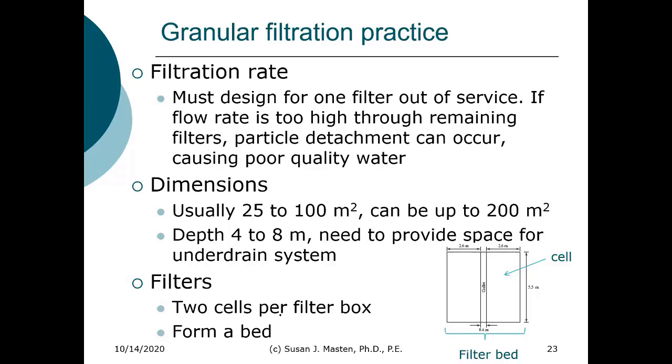And you need to remember that in your design. When in the East Lansing wastewater treatment plant, when they designed those filters, the engineers forgot to consider this. And when they have a high flow, so storm event, and they're backwashing a filter, they have to bypass some of the water around the filter because they can't treat it all, because somebody forgot to do this set of calculations. Don't be that engineer.